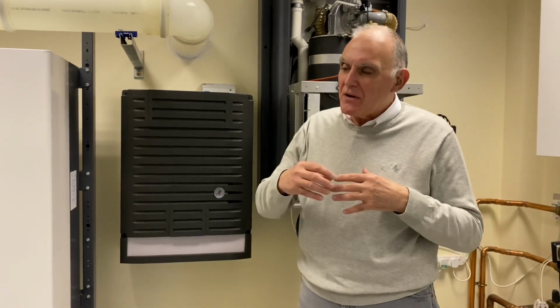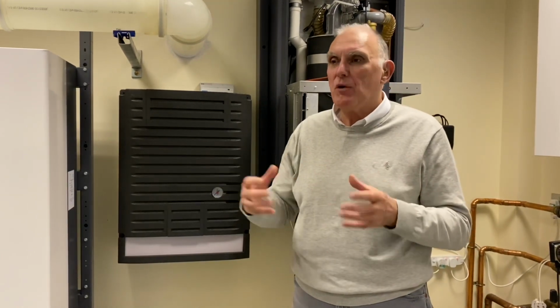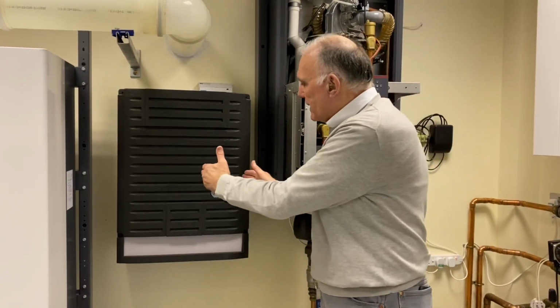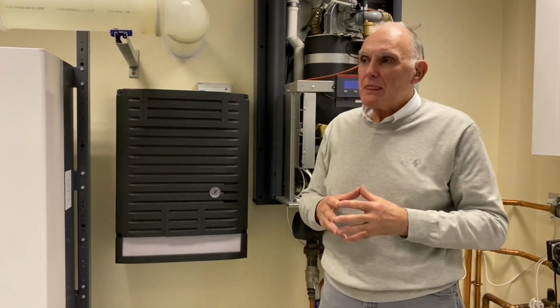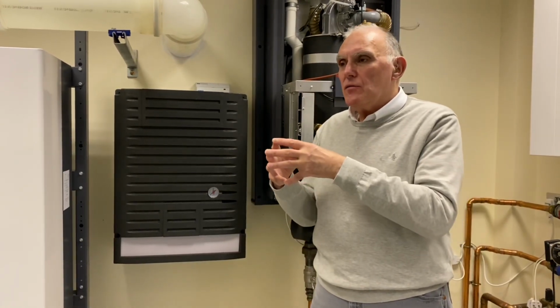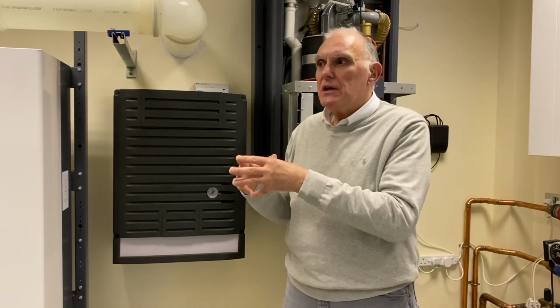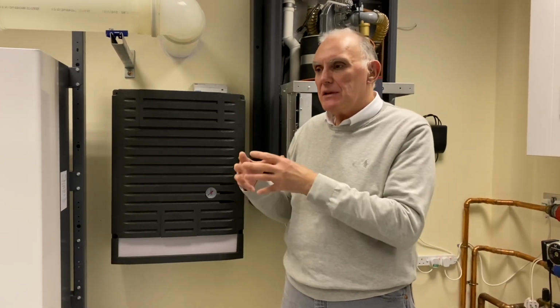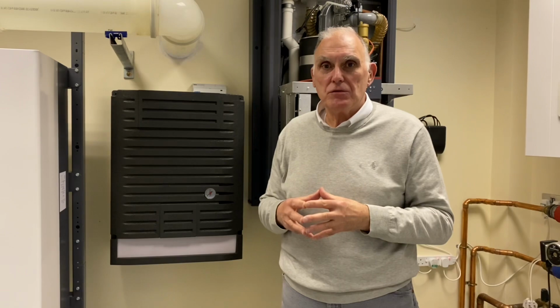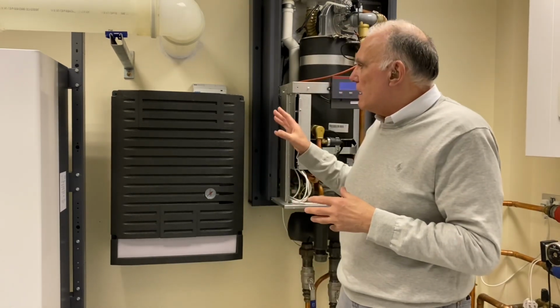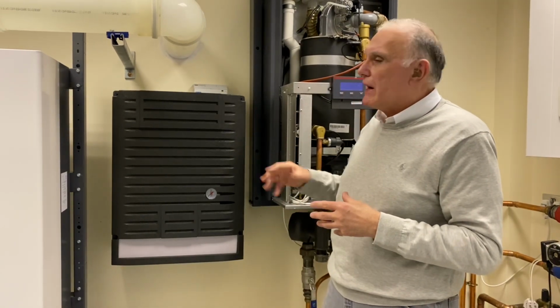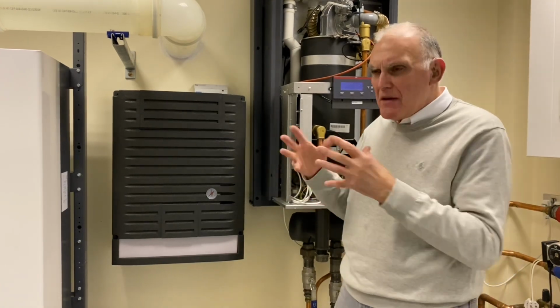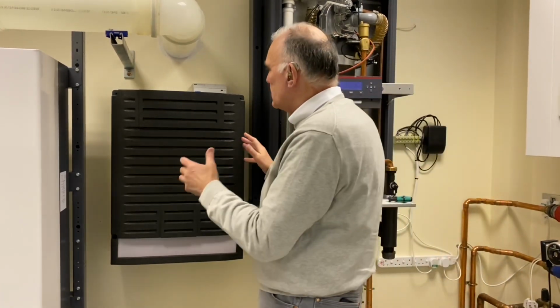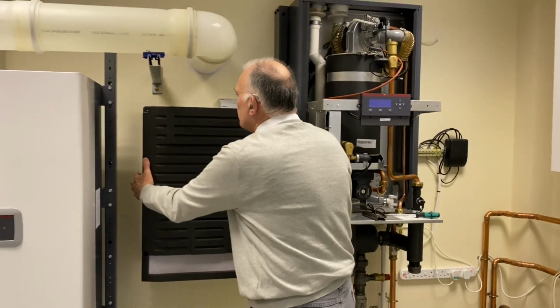The primary flow and returns from the main plant in a boiler house somewhere are taken into the heat interface unit, and there the water usage and the heat usage is monitored and metered, so the end user pays for what they use. So this is our unit here. This one is our indirect unit, has heavy insulation over it. I'll remove the insulation to show you what's inside.